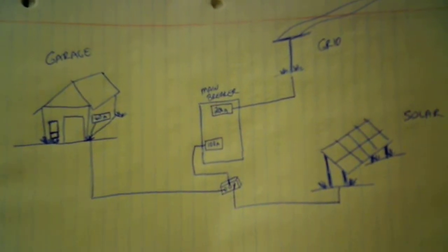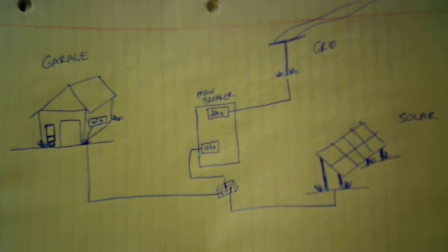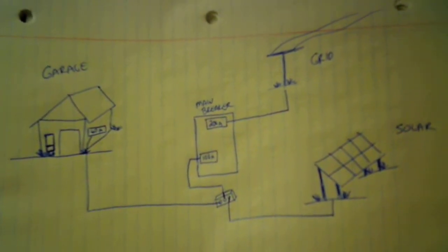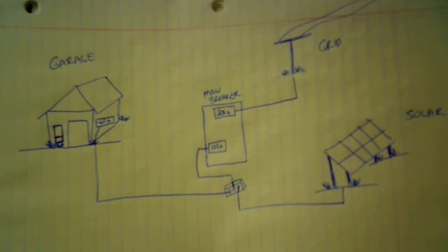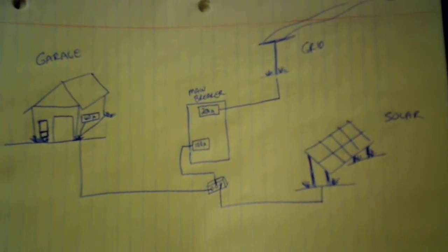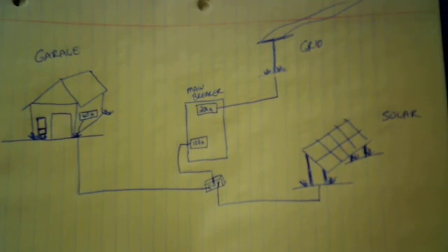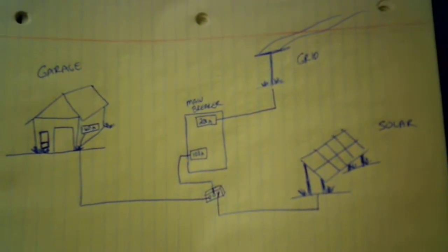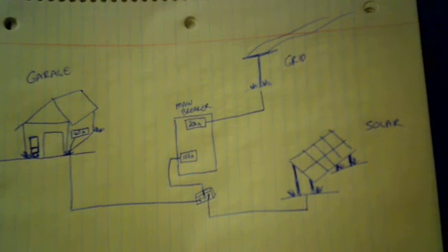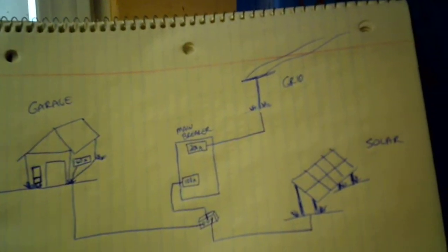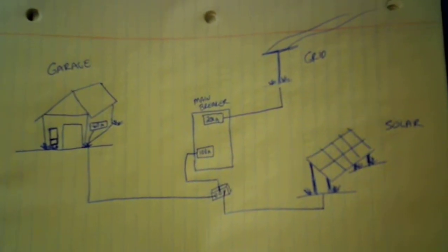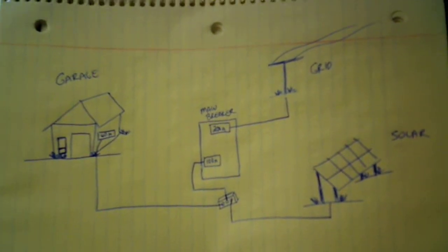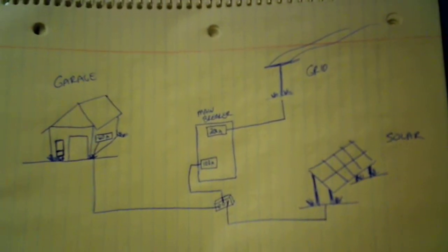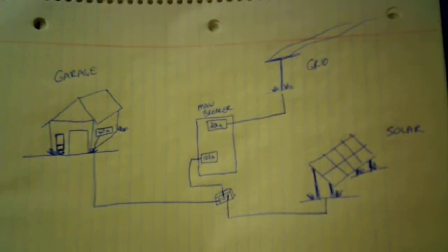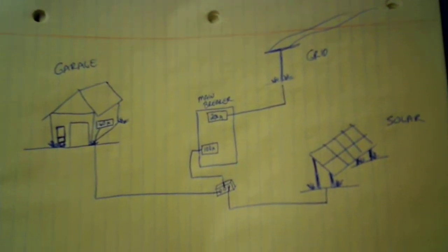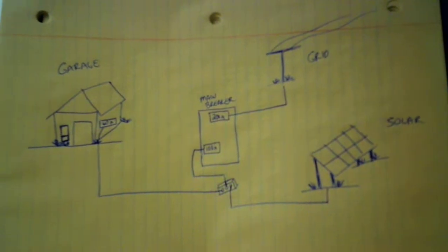I can be completely off grid. If I wanted to do that, I would switch off the 200 amp main service connection, disconnecting myself from the grid. The inverter and all these batteries in the garage would feed in through the junction box, backfeed through that 100 amp service sub-panel circuit breaker, and run the house. The solar panels would do what they do. If it's during the day, they would charge. They would feed power into the house, run all the circuits in there, feed power into the garage, run the circuits in there, and if there's anything left, it'll charge the batteries. That's what we've got going now.